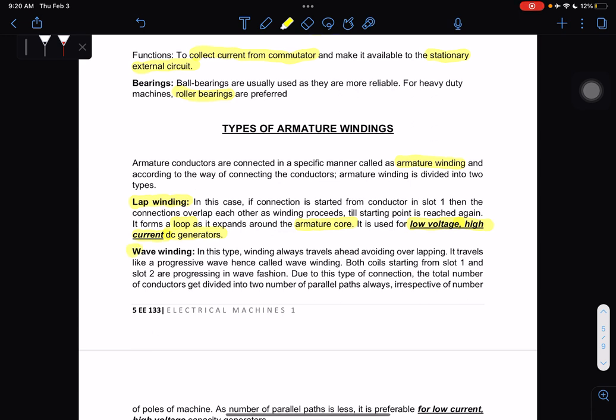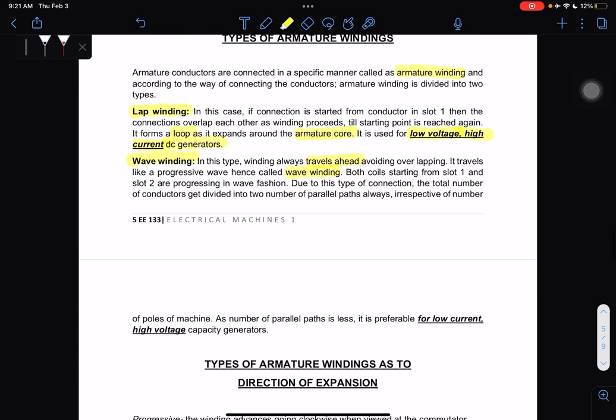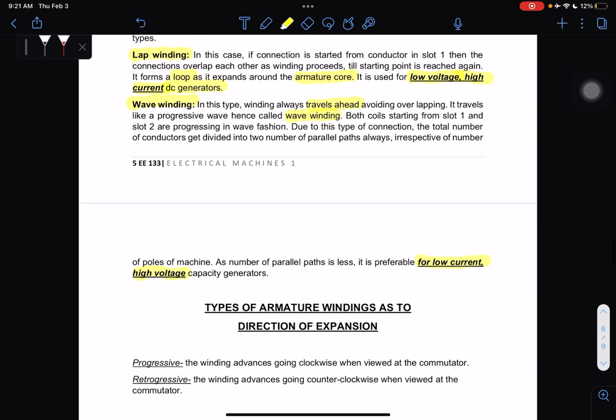The next type is wave winding. In this type, the winding always travels ahead to avoid overlapping — it travels like a progressive wave, hence called wave winding. Both coils starting from slot one and slot two are progressing in wave fashion. As the number of parallel paths is less, it is preferable for low-current, high-voltage capacity generators.